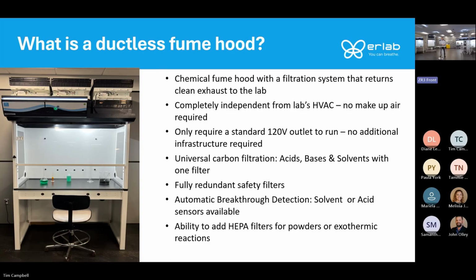What sets Erlab apart from other ductless fume hood manufacturers out there is we have universal carbon filtration. That means you can capture acids, bases, and solvents all with one filter. And the other part that sets us apart is the safety redundancy we have by allowing you to put backup filters on top of the fan box. So in that picture there, that's our Captair 483. That's our 4-foot equivalent hood. It's behind me here in the corner.